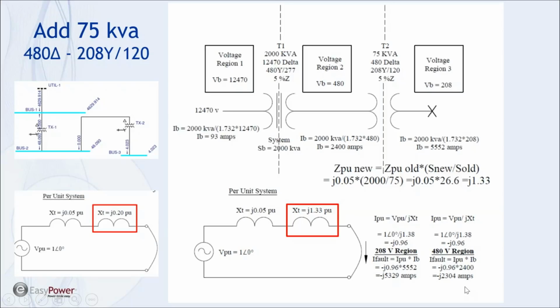On the 480 system, the same per unit current times the 2,400 amps of the base current in that voltage region gives us 2,304 amps. And again, this is what really catches my attention. When I add smaller and smaller transformers, the impedance of those transformers looks really high to the system. And that's one of the tools that I carry in my bag as I go about my business doing safety work and working with people to implement safety plans.